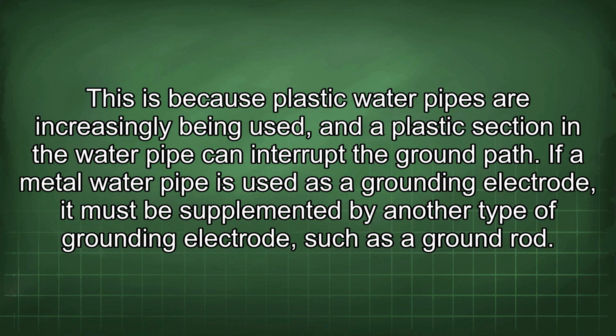This is because plastic water pipes are increasingly being used, and a plastic section in the water pipe can interrupt the ground path. If a metal water pipe is used as a grounding electrode, it must be supplemented by another type of grounding electrode, such as a ground rod.